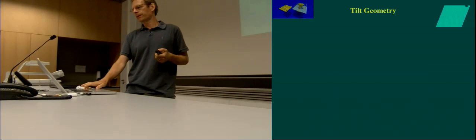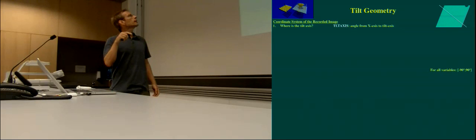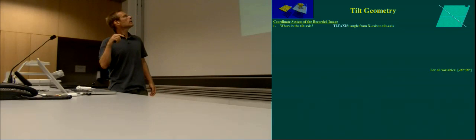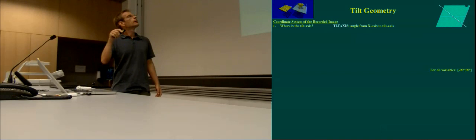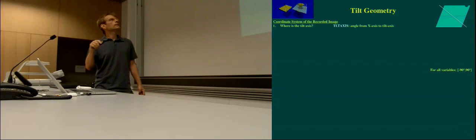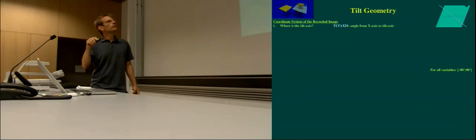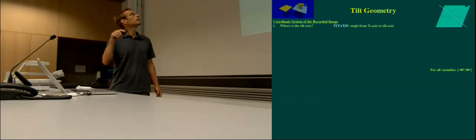You need to be able to measure and quantify that and tell it to the MRC software. Richard Henderson came up with a convention. The slides and recording will be on the server later, so you don't have to take notes. He said the first thing you need to know is the tilt axis. This is your film from the microscope with a little notch — the Kodak film — with a horizontal X axis and a Y axis. The tilt axis is specified by a variable called TLT axis, measuring the angle from the X axis to the tilt axis. In this case it would be minus 30 degrees. Positive in mathematics is always counterclockwise.